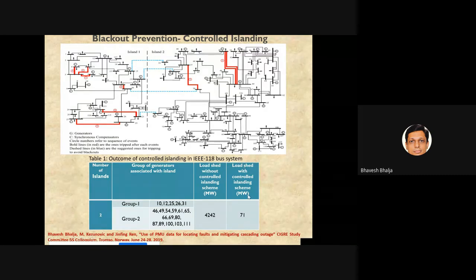But if we go for control islanding, meaning if I use this scheme and trip maybe one or two lines, then the load shed requirement is of the order of 70 megawatts. Earlier you had to remove load of the order of close to 4000 plus megawatts. So this is the advantage of such an intentional or controlled islanding algorithm.